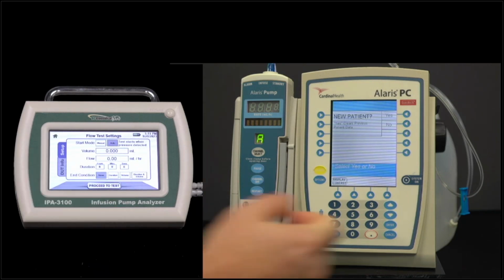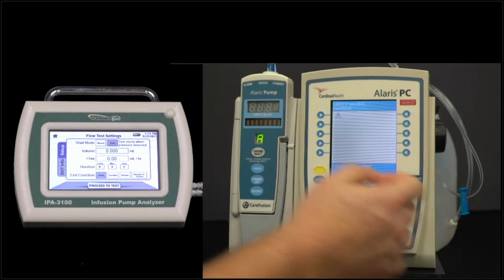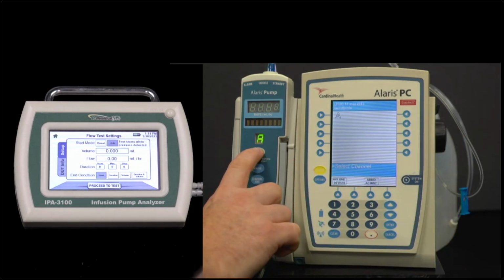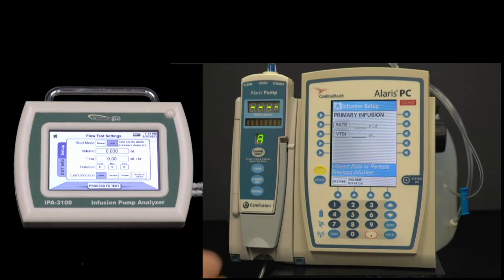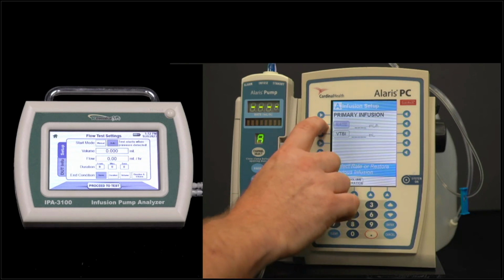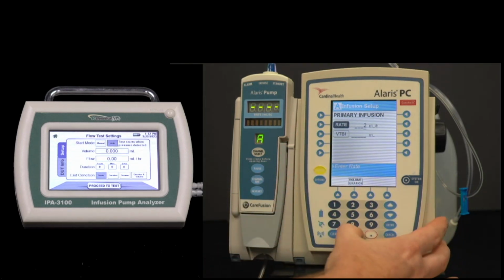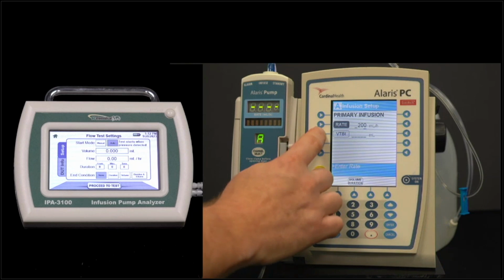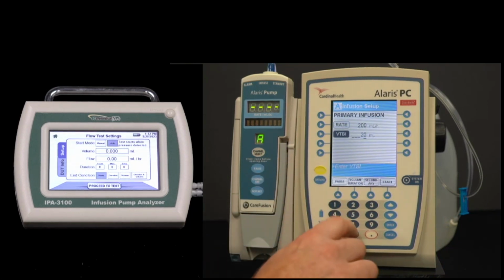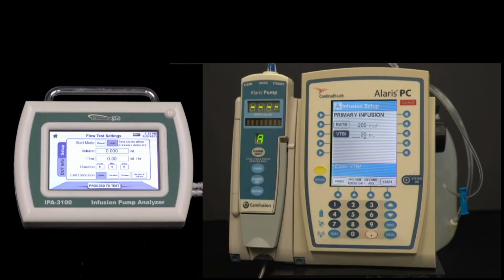Okay. So I'm going to tell it that we're not a new patient, and we're going to test channel A. Now, on the pump, I have to configure what is my flow rate, what is my volume that I'm infusing. So I'm going to go ahead and pick the flow rate. We'll just do 200 milliliters per hour just to give a number, to have a setting in there.